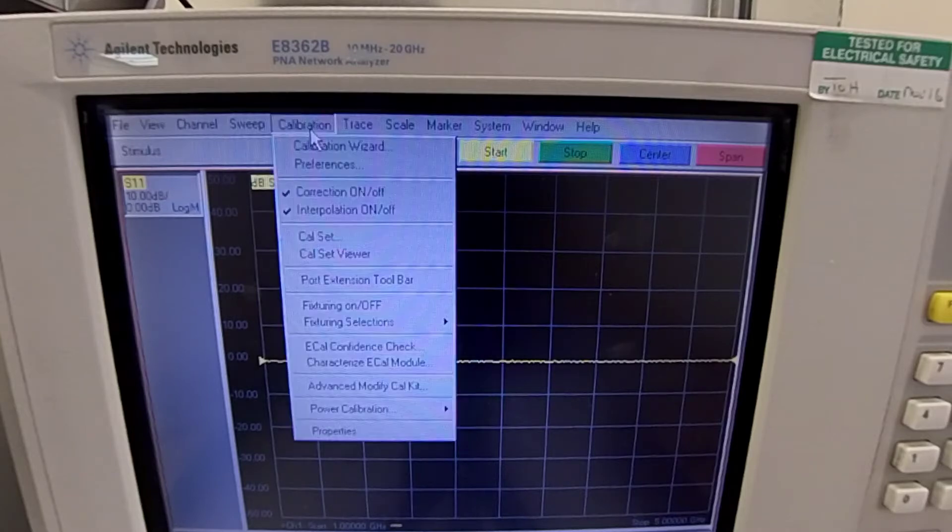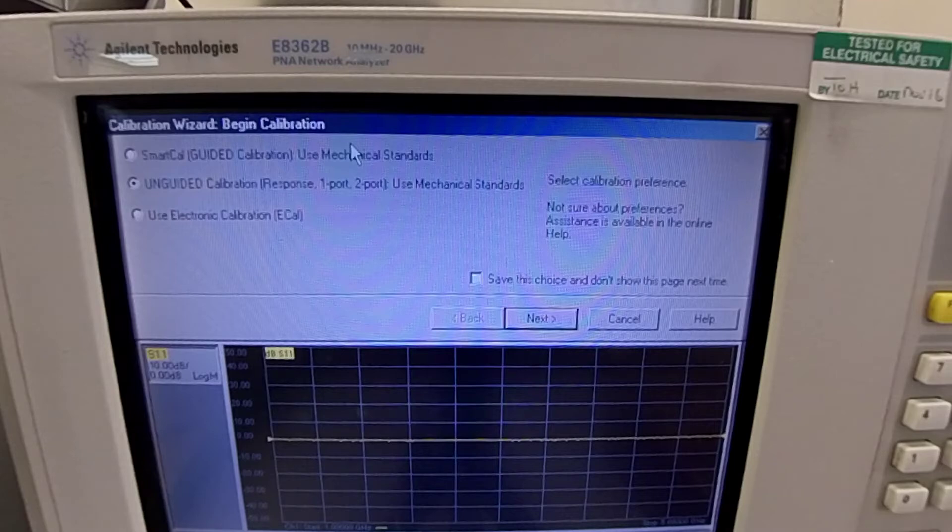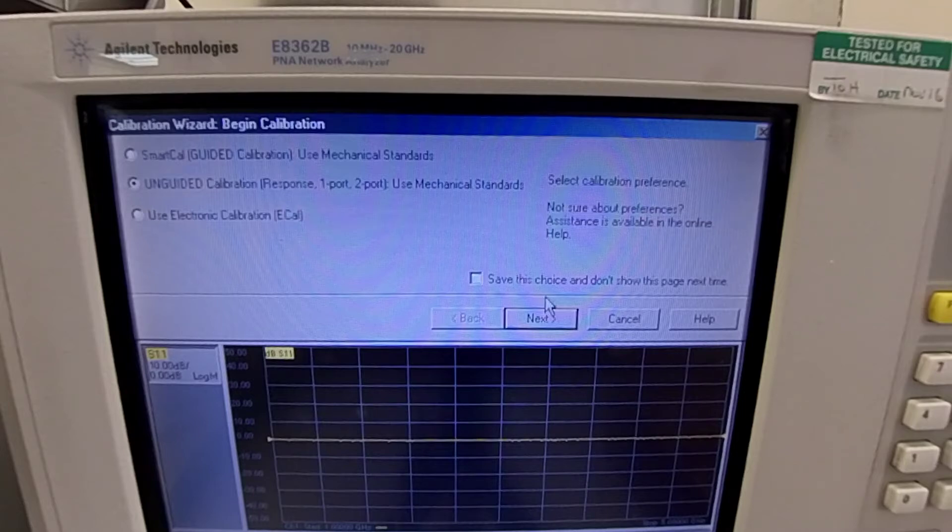Select calibration from the menu and calibration wizard. As you can see there are three options. We will select unguided calibration, use mechanical standard. Click next.